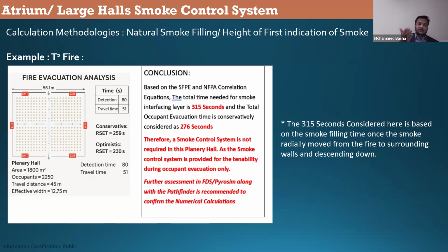It is not that the smoke goes up to some point and then descends. No, it will go and hit the ceiling because the buoyancy of the smoke is higher than the surrounding air. It's a physics principle. Basically, hot air is less dense than the surrounding air, so it will rise up. The same happens with smoke. It's like a chimney in industrial facilities where hot smoke gases rise up, or, for HVAC engineers, the air coming out of a cooling tower. It is similar. It will go to a point, then scatter horizontally.